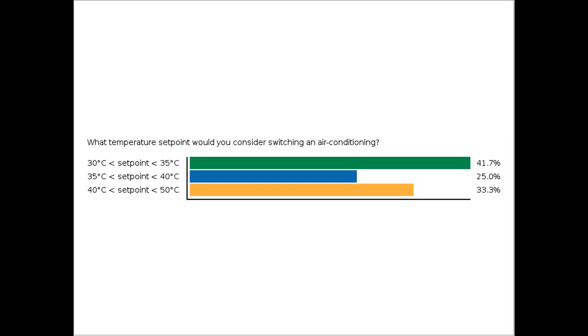So again, very interesting. We can see that there are very widespread air conditioning set point requirements. That certainly depends on the criticality of the site, but the more we can delay that air conditioning set point, the better. That is when the air conditioning comes on, when the energy hungry compressor comes on. So I'll take you through our thought process to ensure that we can delay that set point as much as possible, and how we can actually do it.